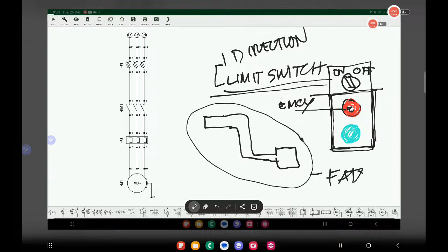Normally, you rotate the manual handle to turn the shaft until it is home. But this manual handle sometimes causes fatal accidents, when people forget to remove it from the shaft and the electrical motor starts running at 1750 rpm or more, 3600 or whatever is on its nameplate. Once the motor starts rotating, the handle will fly off with extreme force, and if it hits your body or head, it will cause a really serious accident.